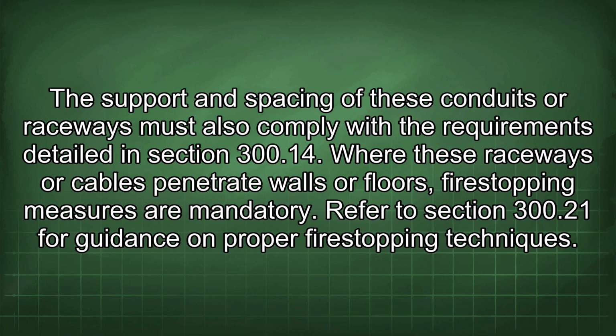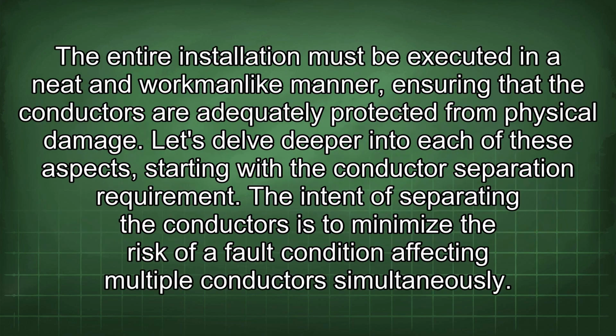Where these raceways or cables penetrate walls or floors, fire-stopping measures are mandatory. Refer to section 300.21 for guidance on proper fire-stopping techniques. The entire installation must be executed in a neat and workmanlike manner, ensuring that the conductors are adequately protected from physical damage. Let's delve deeper into each of these aspects, starting with the conductor separation requirement.